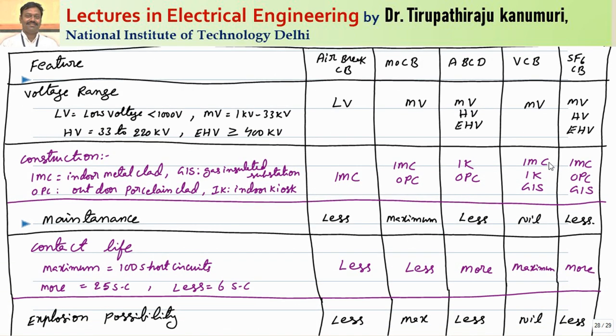Let us summarize the features of these circuit breakers. Voltage range: LV means low voltage up to 1000 V, MV means medium voltage up to 33 kV, HV means up to 220 kV, and EHV is greater than or equal to 400 kV. For construction types: IMC stands for indoor metal clad, OPC stands for outdoor porcelain clad, GIS stands for gas insulated substation, and IK stands for indoor kiosk. Air brake circuit breakers are used for low voltage applications, minimum oil circuit breakers for medium voltage up to 33 kV, and air blast for medium, high, and extra high voltage.